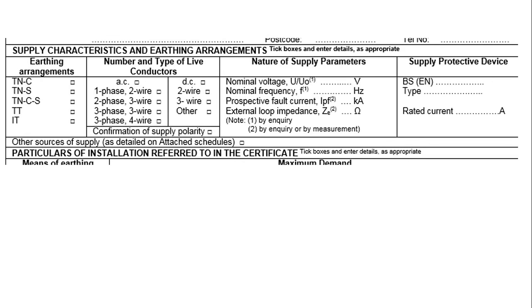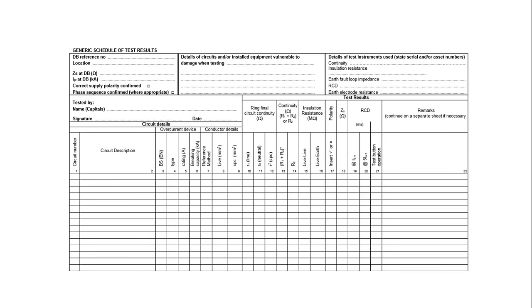I'll just show you where it goes on the electrical installation certificate — either on page one or page two, depending on which certificate you're using. You can see a little tick box: confirmation of supply polarity. As we've just proven it with that previous test, we can put a little tick in the box there. There's also a box on the schedule of test results in the top left-hand corner. Once you've confirmed supply polarity, we can put a tick in that box as well to confirm that the supply polarity is correct.